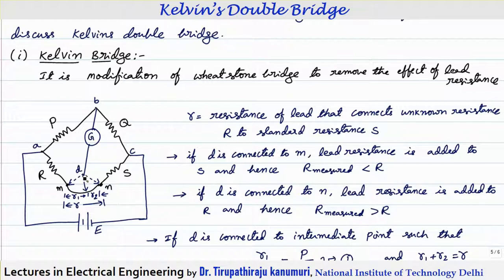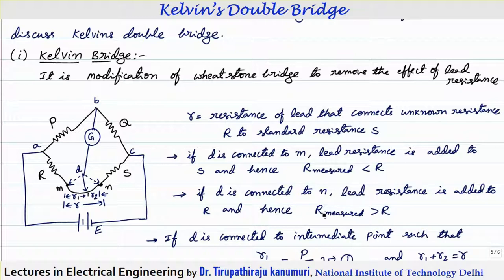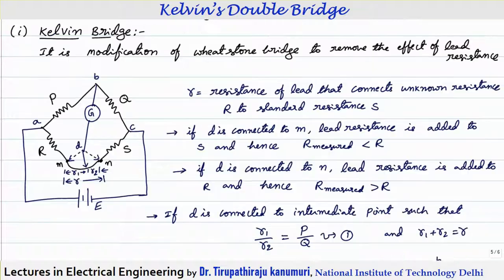If galvanometer point D is connected to the unknown resistor terminal, then the entire lead resistance r will be connected as part of the standard resistance. Since this resistance is included but not considered, the measured value of resistance will be less than the actual value. Alternatively, if point D is connected to the standard resistor terminal N, then this lead resistance will add to R, making the measured resistance equal to R plus small r — greater than capital R. So in both cases, we are getting error.